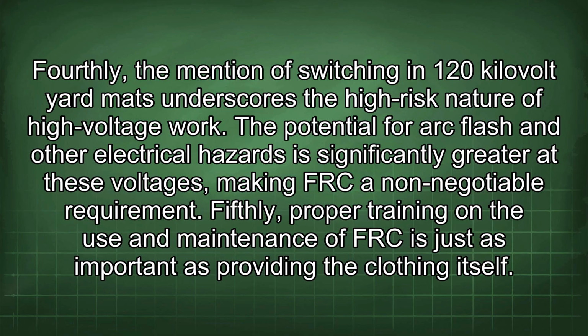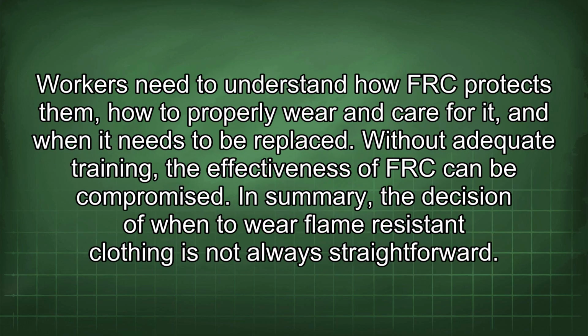Fourthly, the mention of switching in 120 kV yard mats underscores the high-risk nature of high-voltage work. The potential for arc flash and other electrical hazards is significantly greater at these voltages, making FRC a non-negotiable requirement. Fifthly, proper training on the use and maintenance of FRC is just as important as providing the clothing itself. Workers need to understand how FRC protects them, how to properly wear and care for it, and when it needs to be replaced. Without adequate training, the effectiveness of FRC can be compromised.